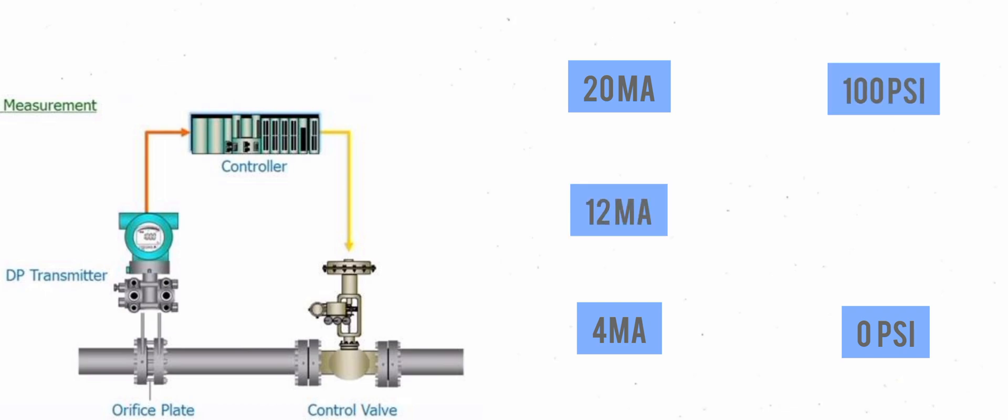Using these variables, we would know that a 12 milliamp signal would equal 50 psi. The relationship of the produced electrical signal to the units of measure is called the scaled output.